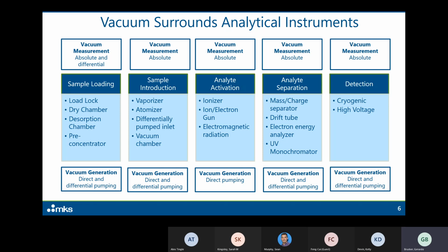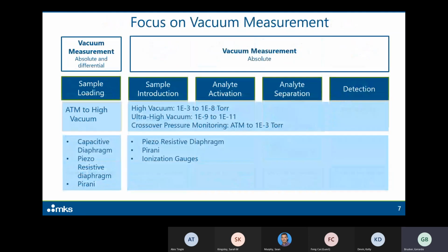So let's talk a little bit about, since I am a pressure measurement kind of guy, the vacuum measurement requirements. The way this breaks down in analytical instruments is we have two main areas that we need to concentrate on. On the sample loading side, because of the load lock requirements and the differential pressure measurement requirements, if we are developing instrumentation for this application, we typically need to measure anywhere from atmospheric to high vacuum. The pressure measurement devices you will find here are things like capacitive diaphragm gauges, piezoresistive diaphragm gauges, and Pirani gauges.